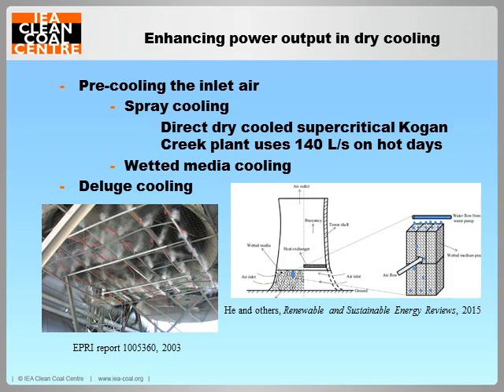The inlet air can be cooled by spraying a small amount of water into the inlet airstream of an air-cooled condenser, where it evaporates and cools the air. This is shown in the figure on the left. Some 140 litres per second of water is consumed on hot days during spray cooling at the direct dry-cooled supercritical Kogan Creek power plant in Australia. But doing this does increase power production by 20 megawatts to give a total output of 740 megawatts.